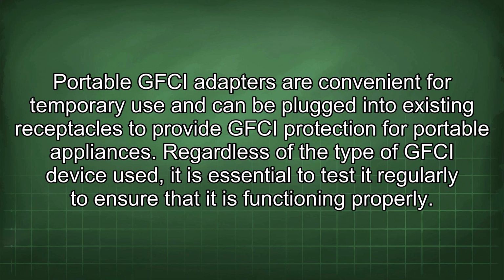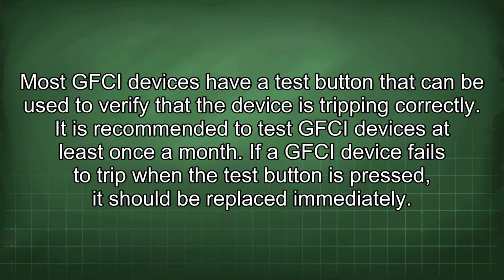portable appliances. Regardless of the type of GFCI device used, it is essential to test it regularly to ensure that it is functioning properly. Most GFCI devices have a test button that can be used to verify that the device is tripping correctly. It is recommended to test GFCI devices at least once a month. If a GFCI device fails to trip when the test button is pressed, it should be replaced immediately.